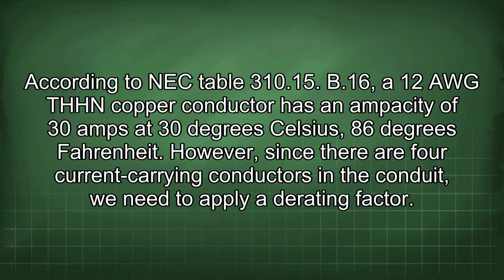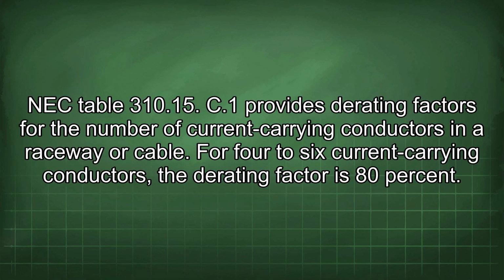According to NEC Table 310.15(B)(16), a 12 AWG THHN copper conductor has an ampacity of 30 amps at 30 degrees Celsius, 86 degrees Fahrenheit. However, since there are 4 current-carrying conductors in the conduit, we need to apply a derating factor. NEC Table 310.15.